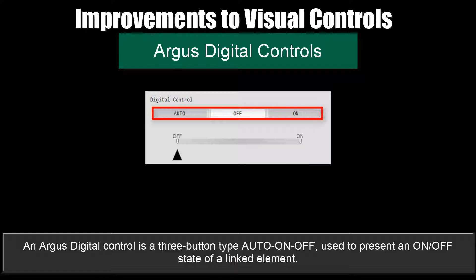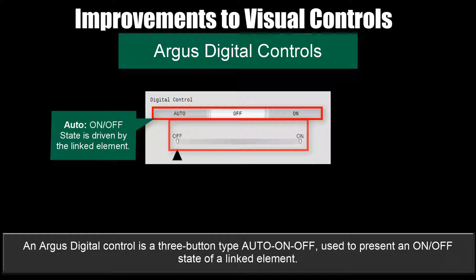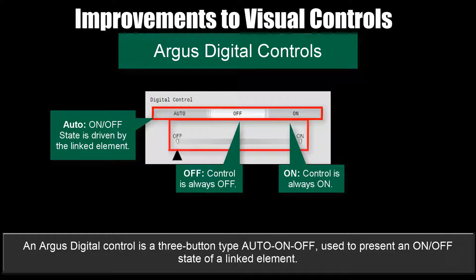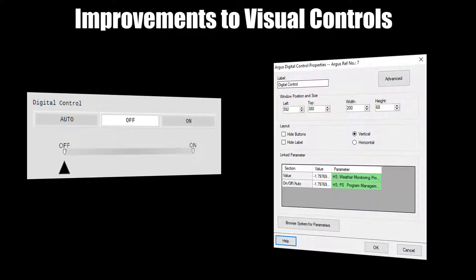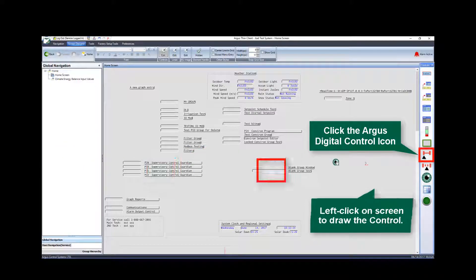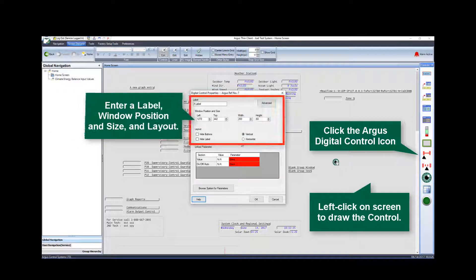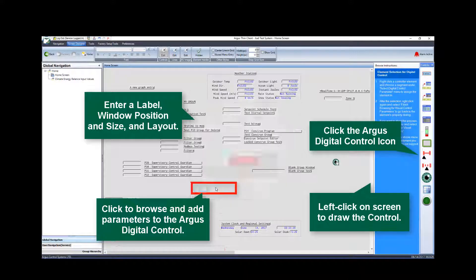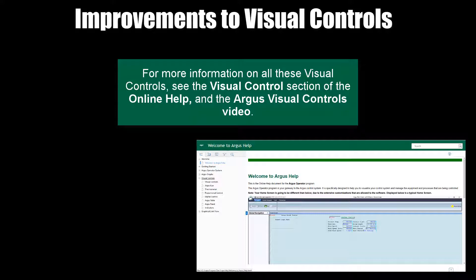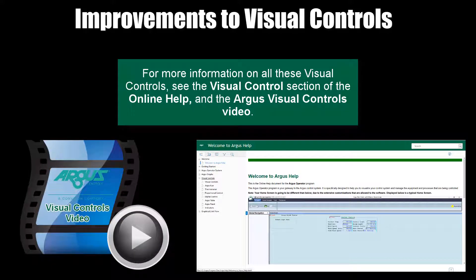An Argus digital control is a three-button type — auto, on, and off — used to present an on-off state of a linked element. If the control is in auto mode, the on-off state is always driven by the linked element. If the off button is pressed, the control is always off; if the on button is pressed, the control is always on. To configure: click the Argus digital control icon, enter a label, window position and size, and layout, then browse and add parameters. For more information on these visual controls, see the visual controls section of the online help and the visual controls video.